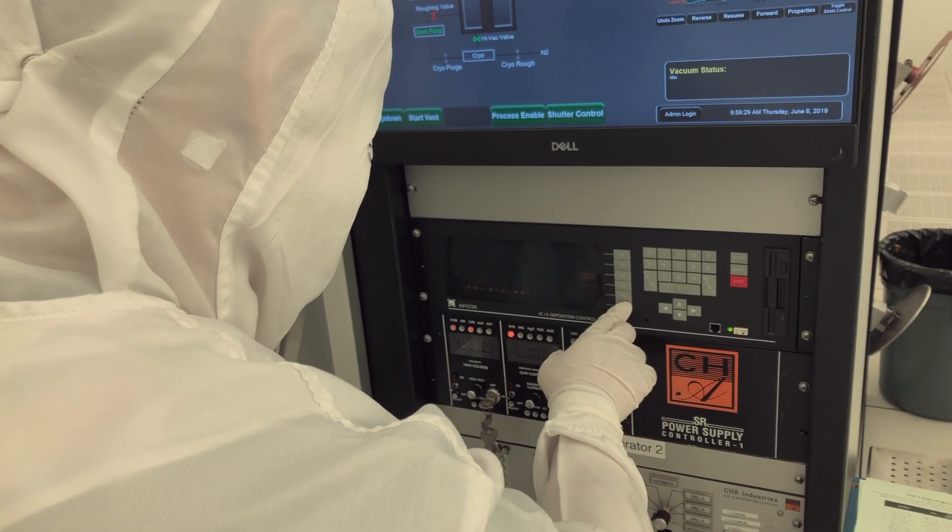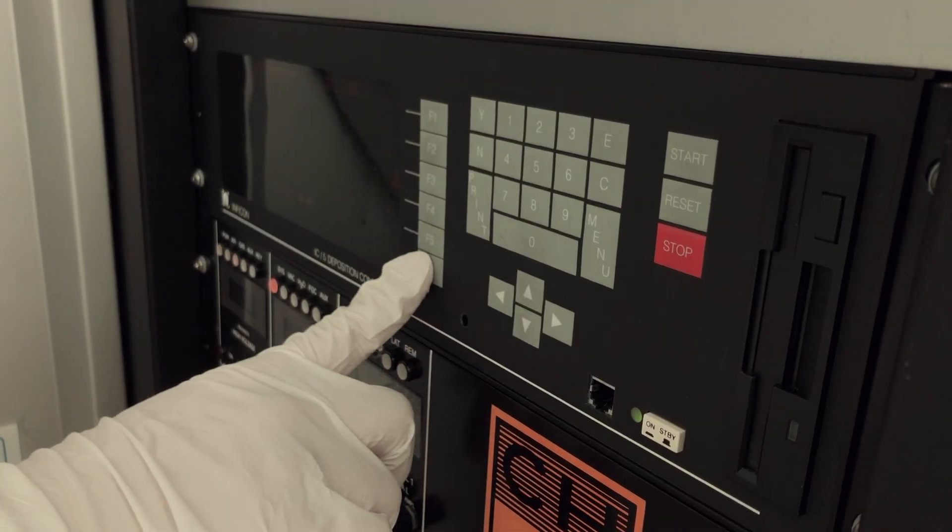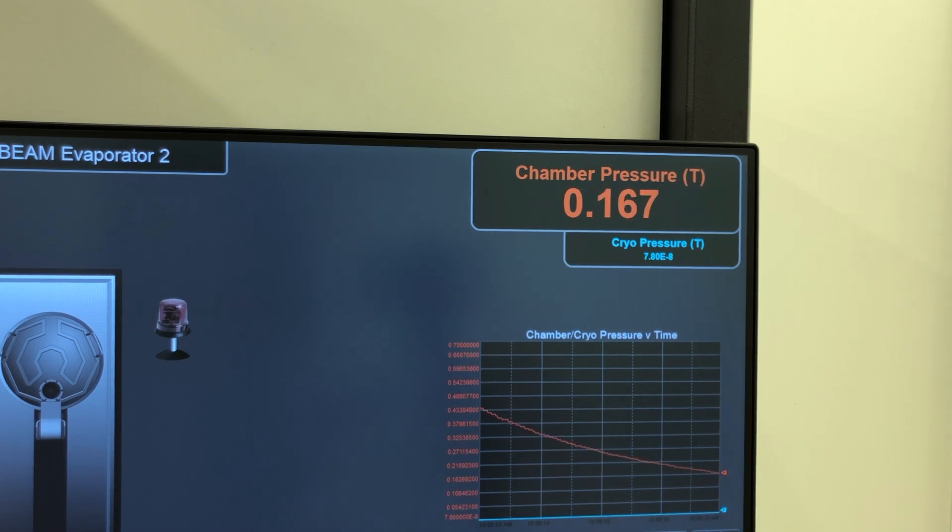Press F6 for program, then press F6 again for operate when you are ready to run your process. You should wait to start depositing material until the pressure is between 10 to the negative 7th to 10 to the negative 8th torr.